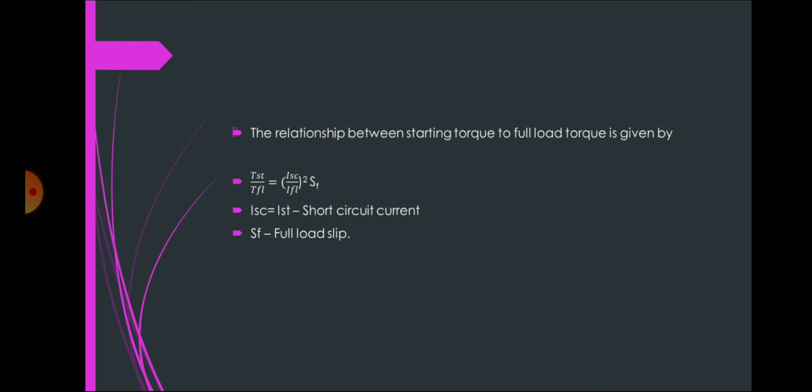The relationship between the starting torque and full load torque is given by TST divided by TFL is equal to ISC divided by IFL, the whole squared, into SF.